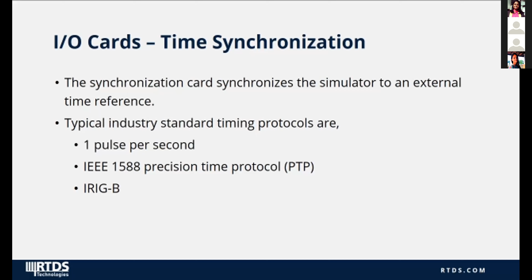It is important to synchronize digital real-time simulators to an external time reference such as a GPS clock. Digital real-time simulators use a high accuracy clock or oscillator to synchronize events to real time. This synchronization ensures that the simulation time step clock remains locked to the GPS signal. It may use industry standard timing protocols such as 1 Pulse Per Second, IEEE 1588 Precision Time Protocol (PTP), and IRIG-B.